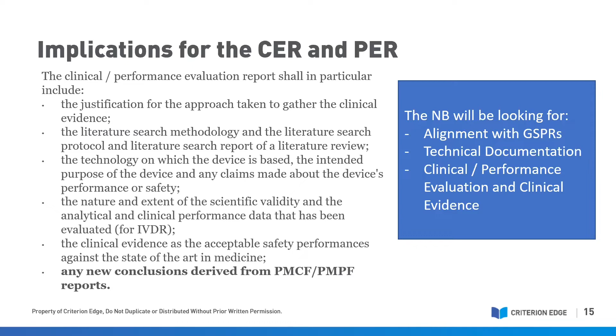And in this case, you may have updated your systematic literature review from the original. And you may also rely on published experience gained by routine diagnostic testing, which could include data from registries and surveys. At least one of the listed methods must be used. Studies performed under IVDD, FDA, or other regulatory regimes may not qualify as clinical performance studies as defined in Annex 13, but they might be used as other sources of clinical performance data, which is also important. If you're going to use these other studies, scientific peer-reviewed literature and/or published experience gained by routine diagnostic testing must be used in combination. Explicit justification for not performing clinical performance studies is required.